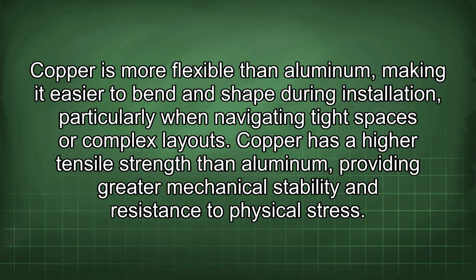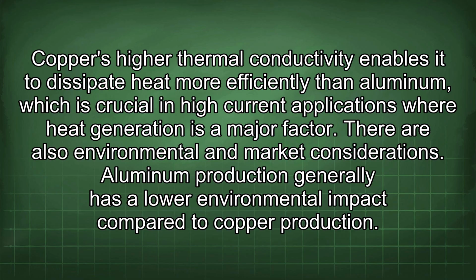Copper is more flexible than aluminum, making it easier to bend and shape during installation, particularly when navigating tight spaces or complex layouts. Copper has a higher tensile strength than aluminum, providing greater mechanical stability and resistance to physical stress. Copper's high thermal conductivity enables it to dissipate heat more efficiently than aluminum, which is crucial in high current applications where heat generation is a major factor.